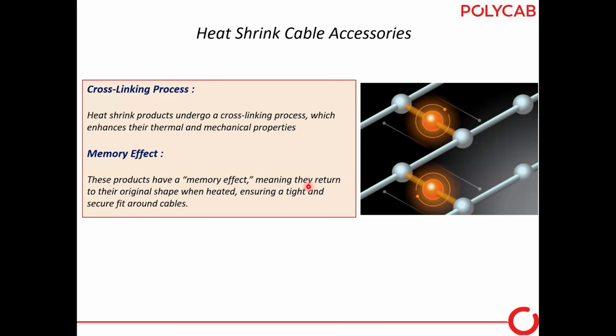Another term always used in heat shrink technology is memory effect. What is the memory effect? When you expand this heat shrink tube at the factory and send it to site, and you again give heat to the tube, it shrinks back to its memory size. For example, if I send one heat shrink tube whose size is 100 by 50, I expanded that tube at the factory by heating to 100 mm. Again, when I heat it at site, it shrinks to 50 square mm only. So that's the memory effect.